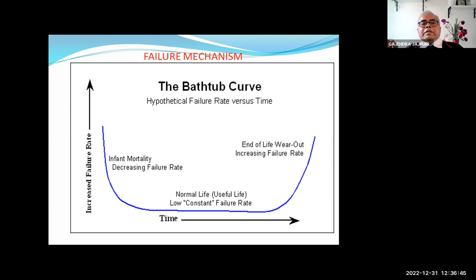Now, for electrical, I have just listed down what can affect failure. Temperature rise, as the photograph indicates, there is some loose contact. Contaminants: as I told in my transformer event, some contaminants ingressed inside the transformer oil, which can cause moisture, and again it will deteriorate the quality of our transformer oil. Or stress, which can be voltage stress or any other stress. Aging can also affect the performance of the electrical equipment.